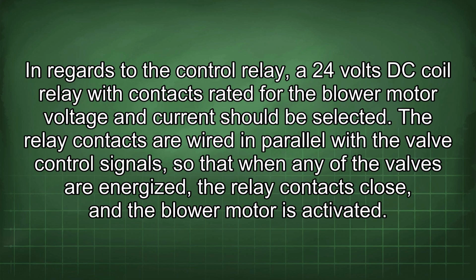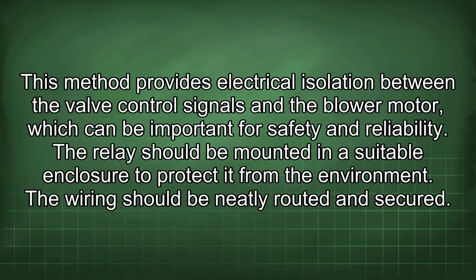In regards to the control relay, a 24 volts DC coil relay with contacts rated for the blower motor voltage and current should be selected. The relay contacts are wired in parallel with the valve control signals so that when any of the valves are energized, the relay contacts close and the blower motor is activated. This method provides electrical isolation between the valve control signals and the blower motor, which can be important for safety and reliability. The relay should be mounted in a suitable enclosure to protect it from the environment.